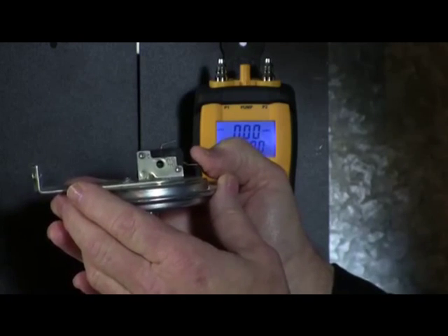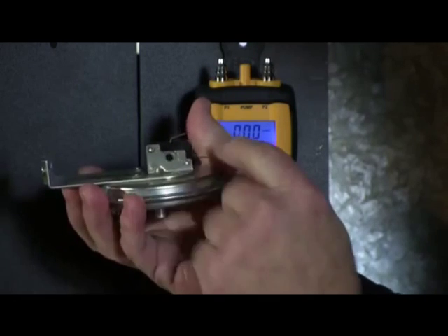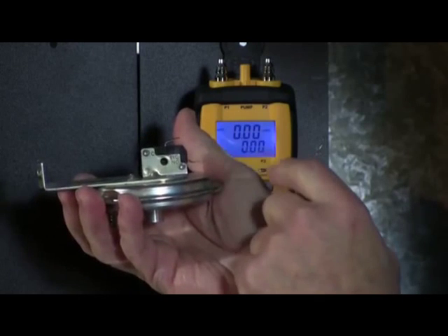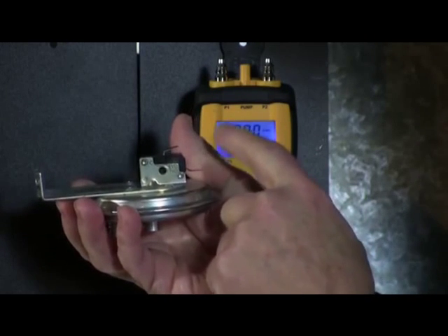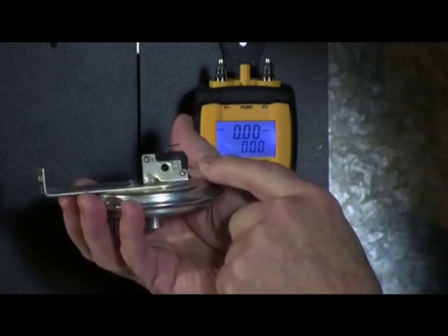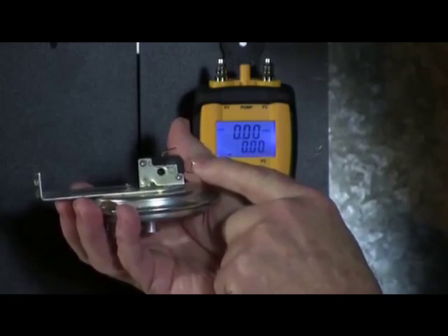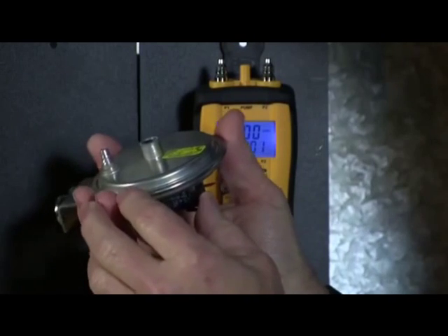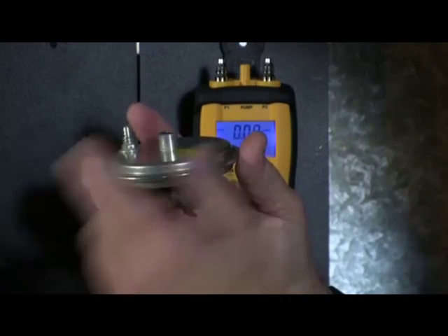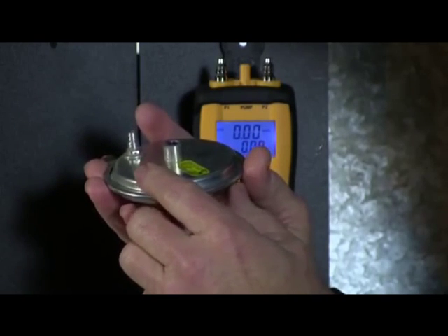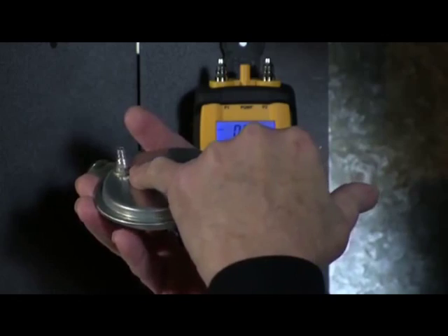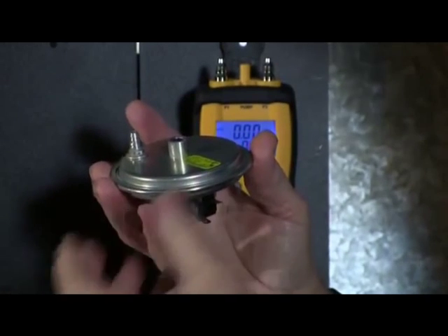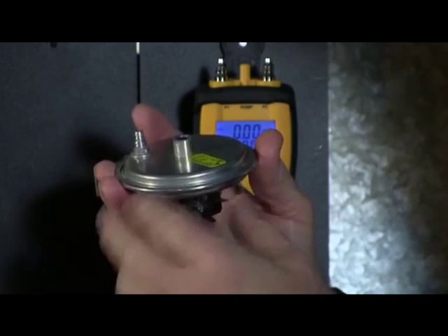Most pressure switches have little bleed ports in them. This one is right here, a tiny little bleed port. That bleed port is used to help regulate when the switch opens and closes. On this one, you can see a little moisture build up. Very important that you do not test a pressure switch with water in it. Just replace it. You don't know what is going on on the inside, and coating could get on the diaphragm.